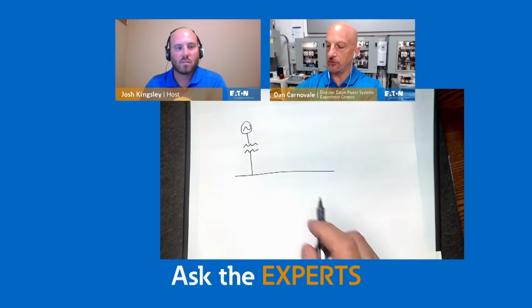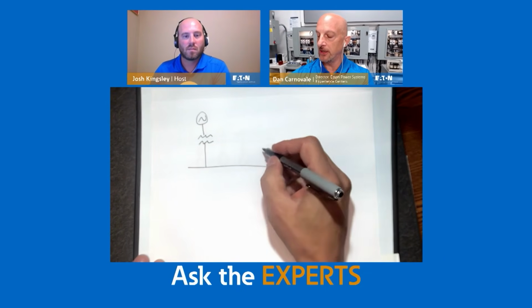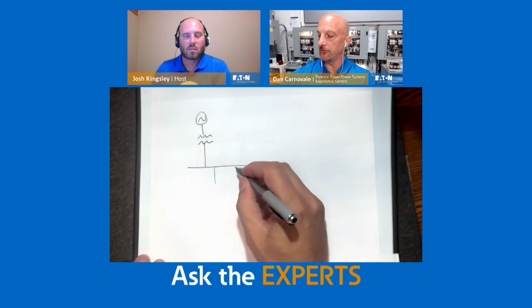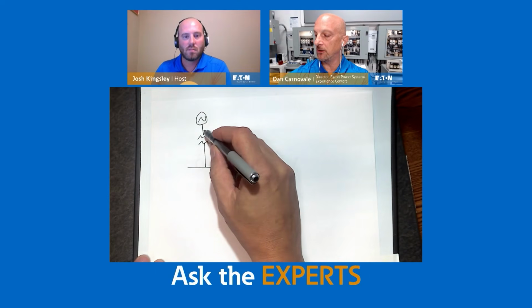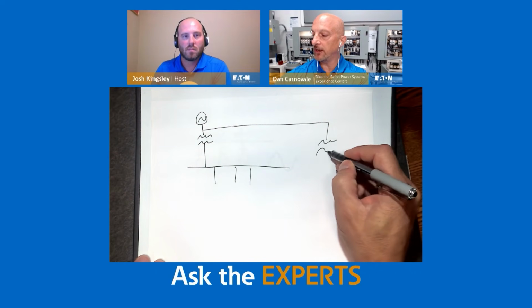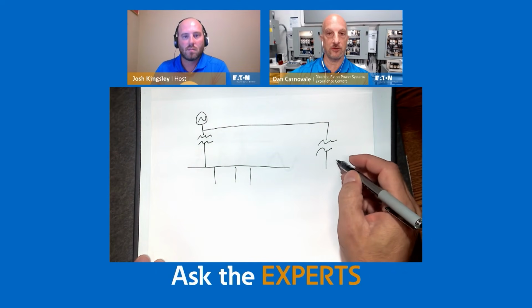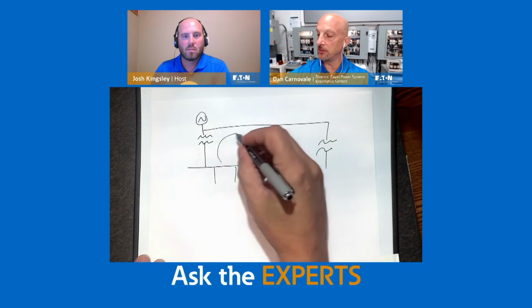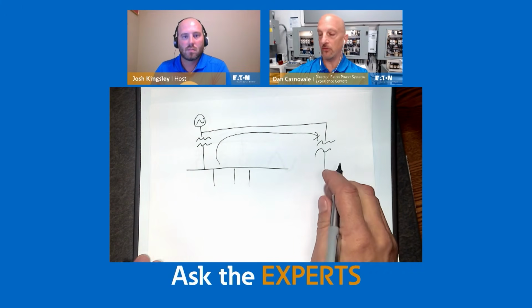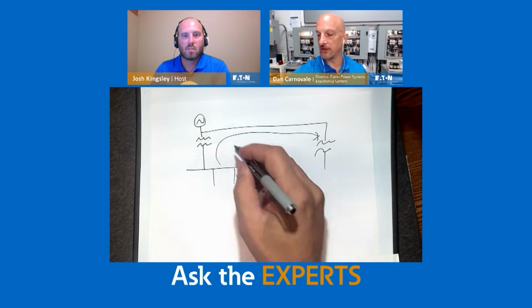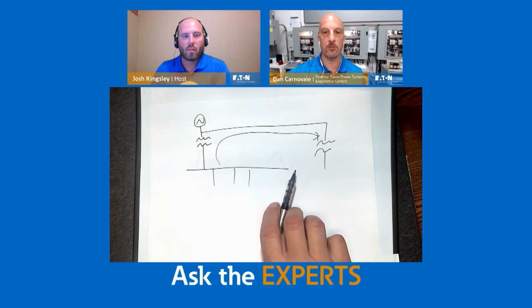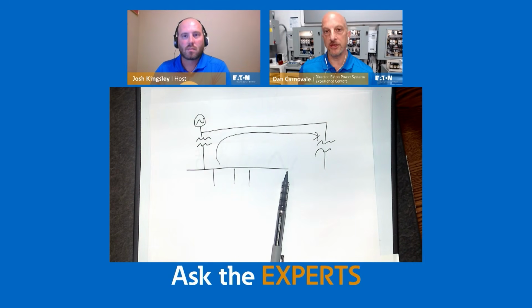Well, that's actually where the IEEE standard comes in. If I go back to a scenario where you have your transformer here, feeding your loads, and on the same system we have another utility customer, you could literally be affecting those guys by your harmonics. That's where the IEEE standard comes in, at the point of common coupling, where they have to be kind of the mediators.